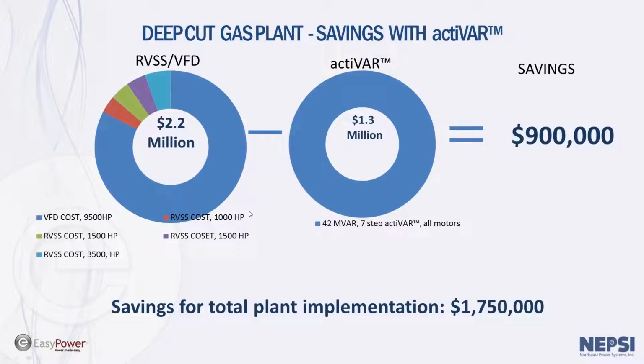And looking at the possible cost savings here, for the A bus, we come up with a cost of $2.2 million versus the actiVAR cost of $1.3 million. So just for the A bus alone, there's a savings of $900,000 here. If you look at the total plant-wide solution, it was about $1.75 million in plant savings. And the system in general is a much simpler system. We have 2 devices instead of 7 soft starts and 2 VFD drives.